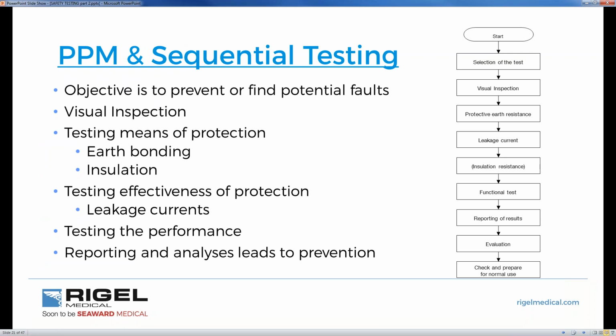So what we have as part of the 62353 is a sequential number of tests. The objective is to find, or at least to prevent, potential faults. We have a visual inspection. We have testing protective means, which is earth bonding and insulation. Insulation, by the way, is not mandatory. It's optional. Some manufacturers use insulation, some don't. You would have to refer to service manuals for that information. And then we have leakage current testing. We have 3 different methods of measuring leakage, and I'll go into that in depth over the next couple of minutes.